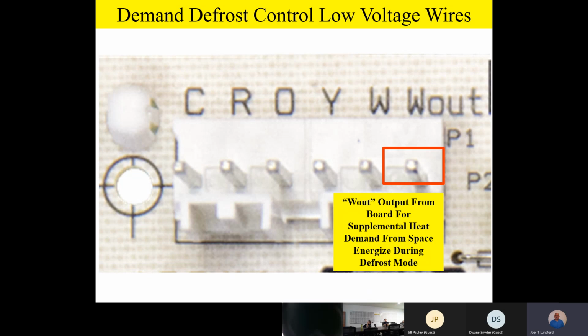In one function, when you get a W from the thermostat that we just talked about, when you get a W on the board, it's going to loop it out through a relay and send it right back inside to bring on the auxiliary heat. Also, when the unit goes into defrost, this is important, it's going to output a W out from the board to bring the auxiliary heat on during defrost.